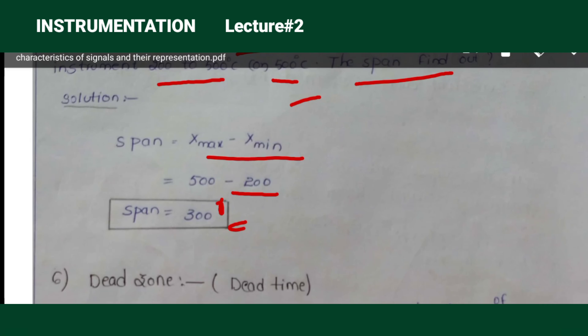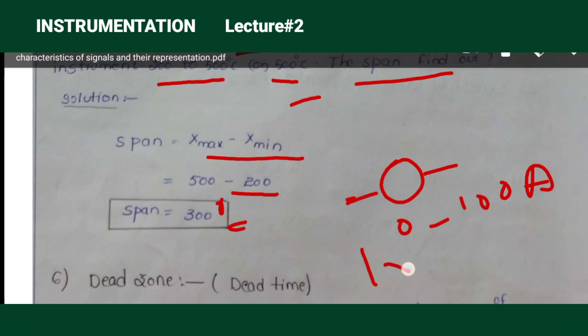Another static characteristic is dead zone, also called dead time. Dead zone is defined as the largest change of input for which the response of the instrument is zero. For example, if an ammeter is rated 0 to 100 amps and you give 1 milliamp, it won't give deflection — that is the dead time of that instrument.